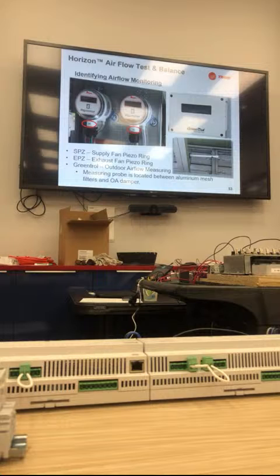Right, so there's three more with the outside airflow not being set. We heard about it last class, and it's happening around the country. Those that should be set in the factory, give us a call and we'll help you set it back up. I've seen several units where the tubes on the left are flip-flopped. That's another issue we're having.